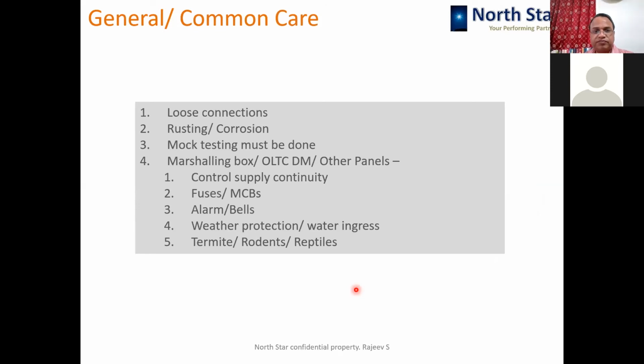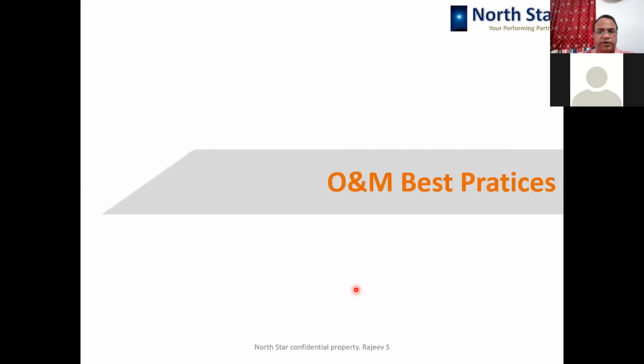those contacts are operating. Okay, so your fuses, MCBs, alarm bells, control supply continuity, cable continuity, these small points, termite, rodents, reptiles. Many times you find that the door of the panel is left open and the termite gets into it. Sometimes rodents also, snakes also are found in the panels. So that causes the malfunctioning of your protection system of the transformer. So this is to be done for a small protection devices maintenance point of view. Protection devices are easy to maintain, but they are required to be maintained, and that has to be included in your routine preventive maintenance program.